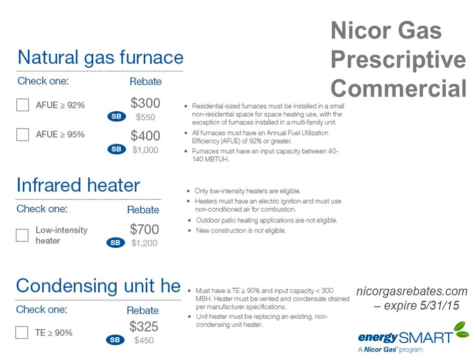Just pay attention to a couple things there. We've had this come up a few times. Outdoor patio heating, which is a great infrared heater application, that is not a rebate eligible thing. This is only for space heating stuff, not for heating the outdoors. And then also make sure that the infrared heater is not using combustion air from space. It's got to be directly piping the combustion air from outdoors, and then obviously exhausting the byproducts outdoors as well.